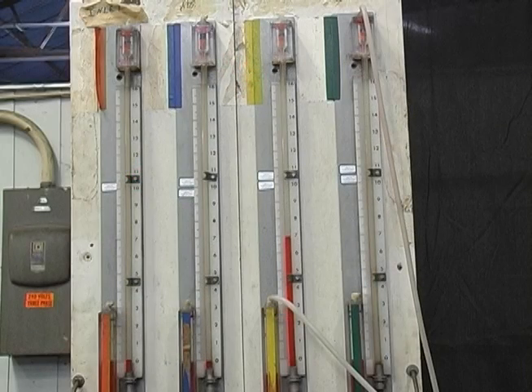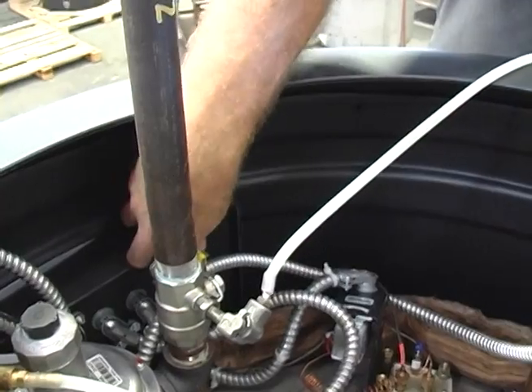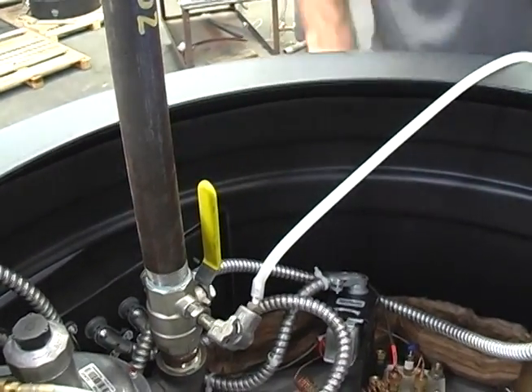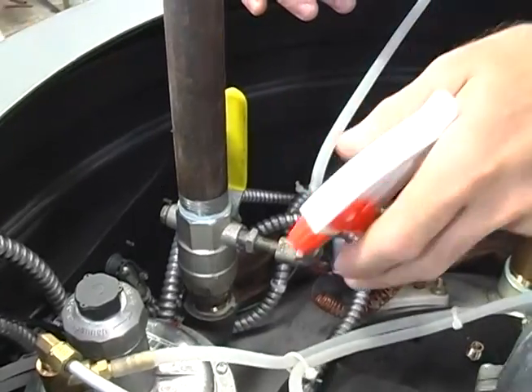The gas pressure at the shutoff valve must be a maximum of 10.5 inches water column. If the supply gas pressure is outside of the allowed range, notify the building maintenance personnel or installer to reduce the gas pressure to the water heater. With the gas pressure properly set, open the main gas supply valve and check the gas train for leaks.